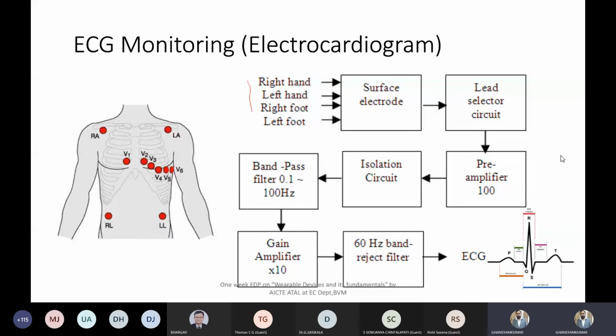Then after the lead selector circuit, as we discussed in the last slide, we need to select which lead is used for that particular ECG signal. And a pre-amplifier is there. An isolation circuit is needed, because when you connect the body with an electrical circuit, isolation circuits are always required to avoid noise. You even need to avoid electrical shock currents and all.